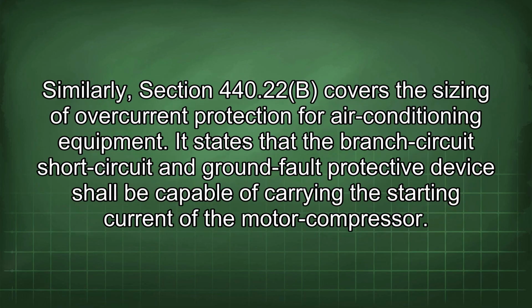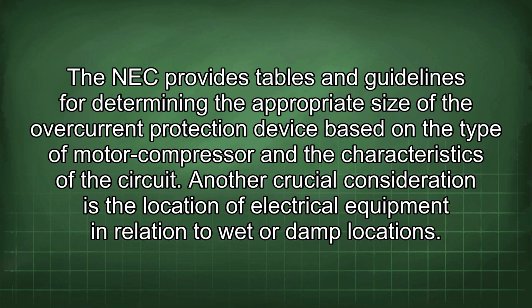This ensures that the conductors can handle the continuous load of the air conditioner without overheating. Similarly, Section 440.22(B) covers the sizing of overcurrent protection for air conditioning equipment. It states that the branch circuit short circuit and ground fault protective device shall be capable of carrying the starting current of the motor compressor. The NEC provides tables and guidelines for determining the appropriate size of the overcurrent protection device based on the type of motor compressor and the characteristics of the circuit.